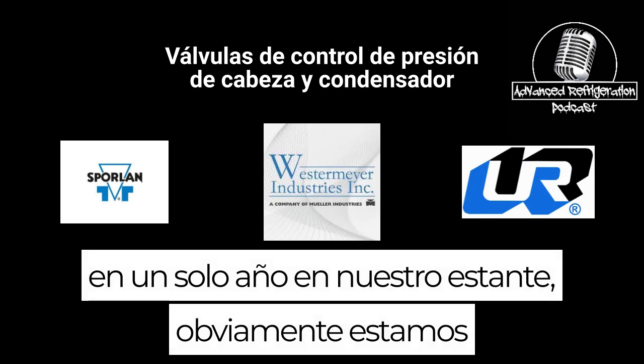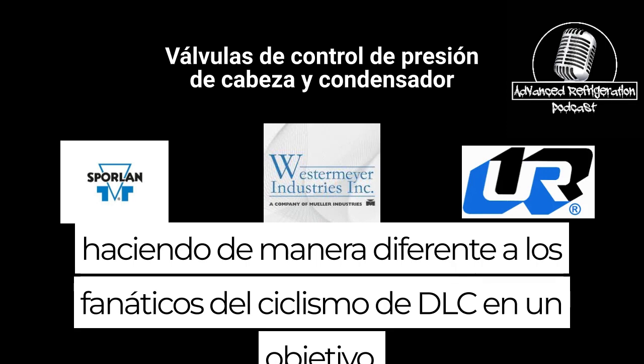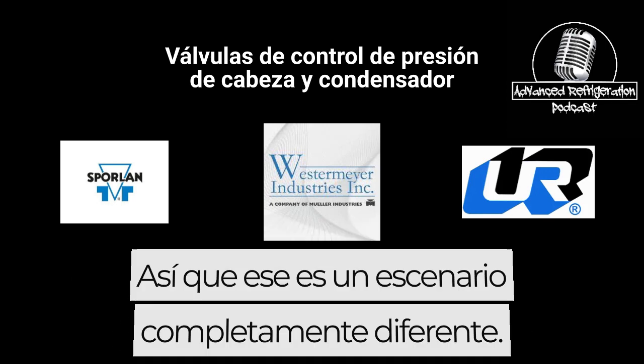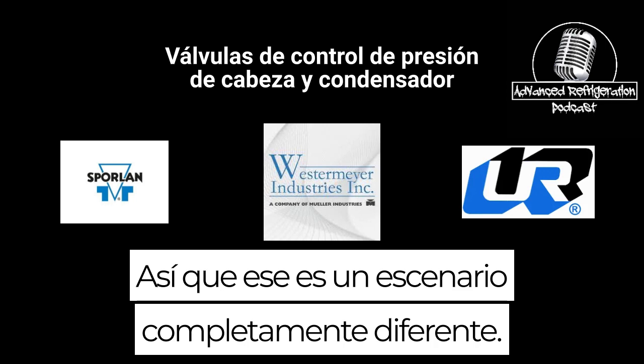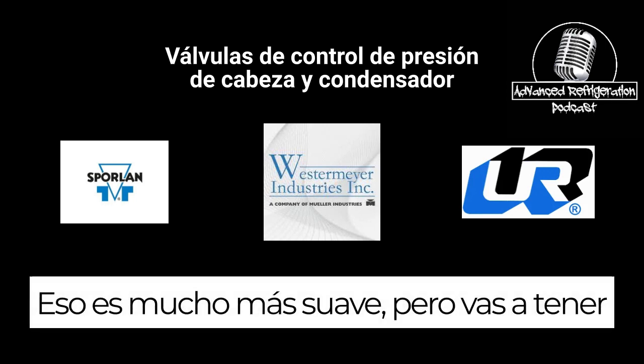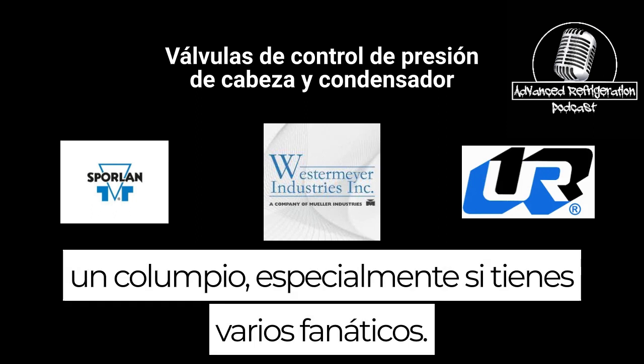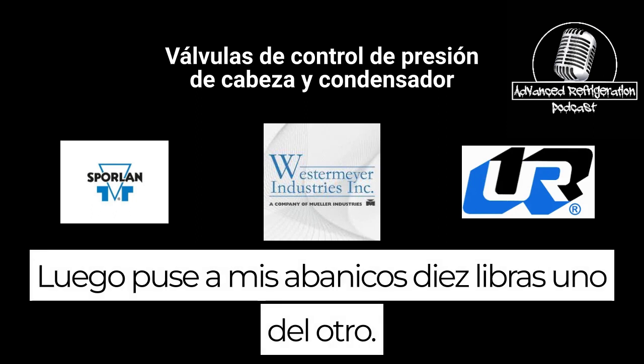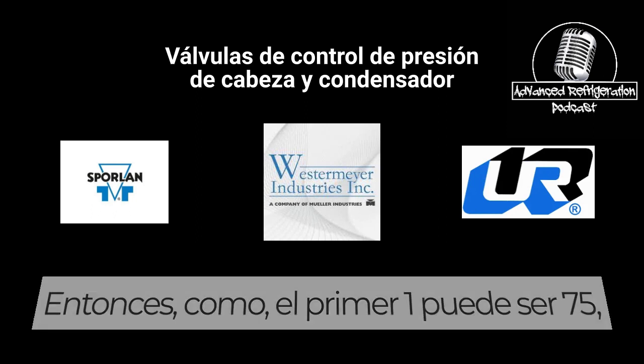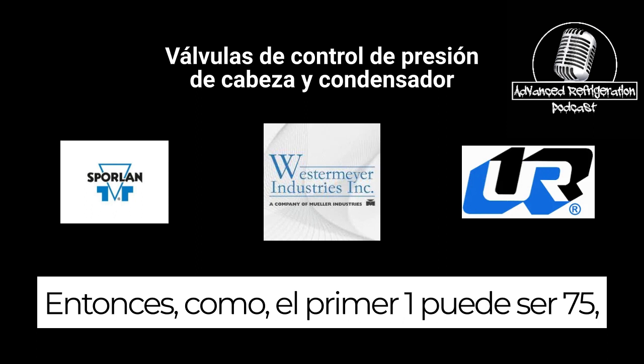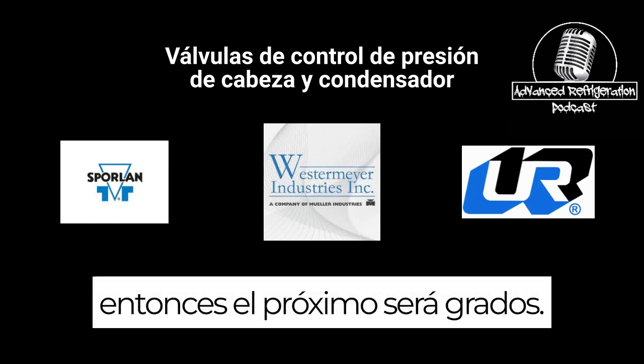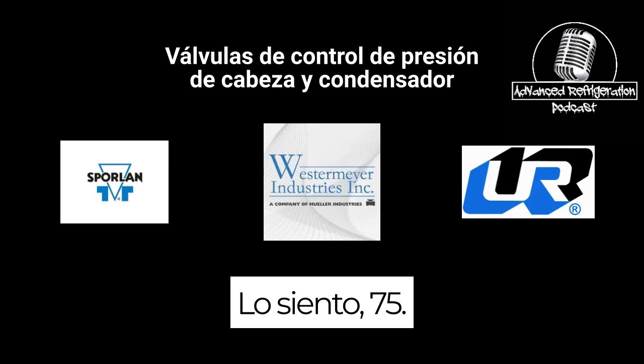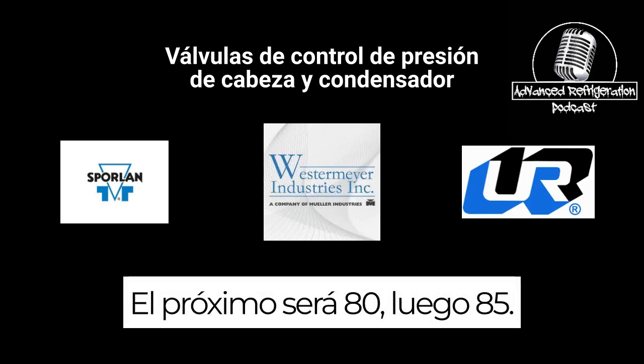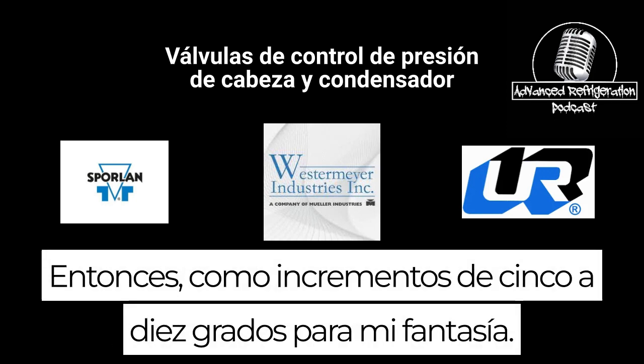On a rack, obviously, we're doing it differently than PLCs cycling fans based on a target. So that's a whole different scenario. That's a lot smoother, but you're going to have a swing, especially if you have multiple fans. Then I set my fans 10 pounds from each other. So like the first one may be 75, next one would be 80, then 85. So like 5 to 10 degree increments for my fan cycling.